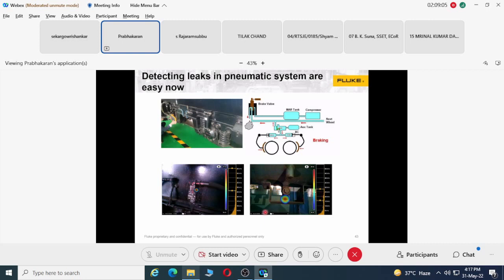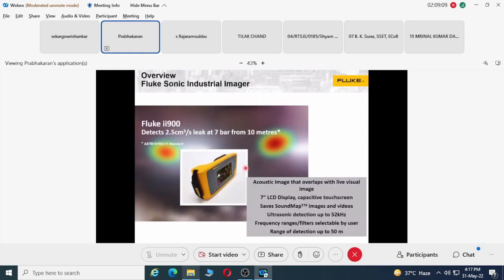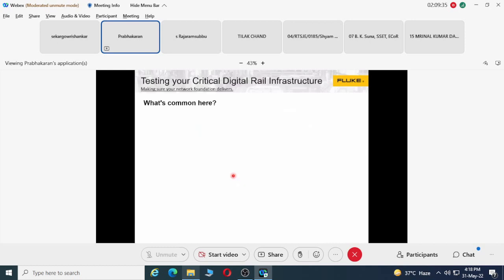Or even if you want to detect partial discharge, the same way you will be able to detect it. This device, we call an acoustic imager or sonic imager, comes with 64 acoustic sensors and a camera, so that from the entire field of view it will capture those sound waves and then show in the visual image from where it is coming. That is how it helps you find the leaks.